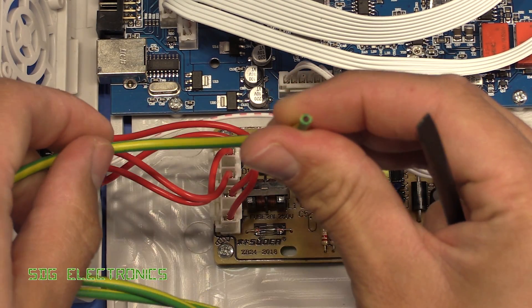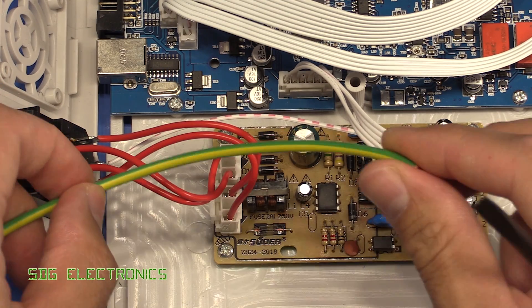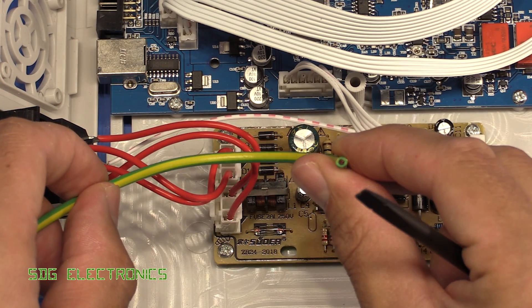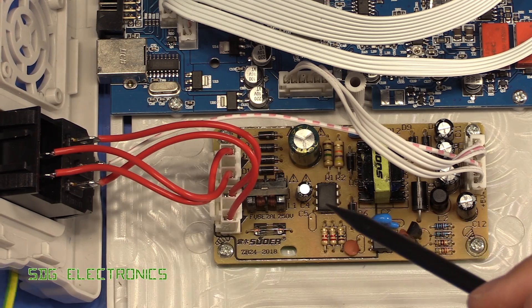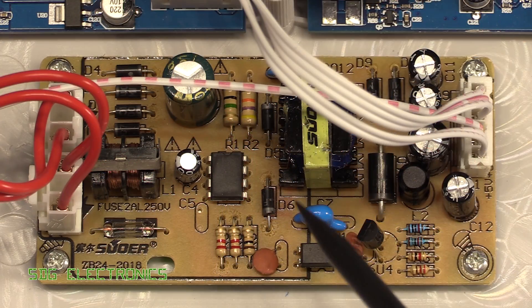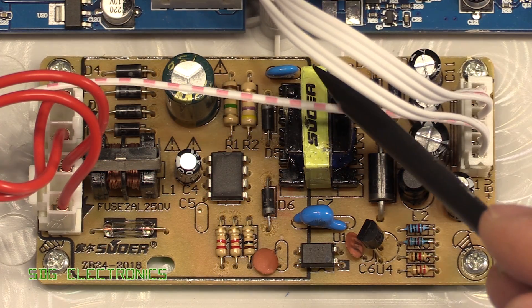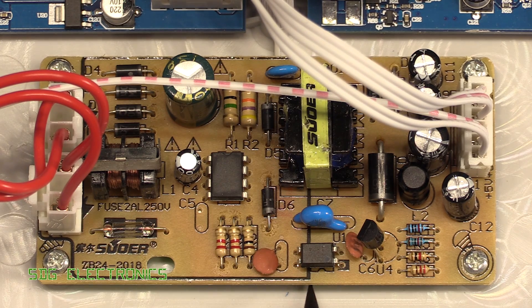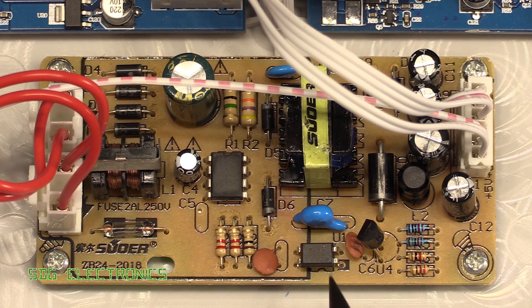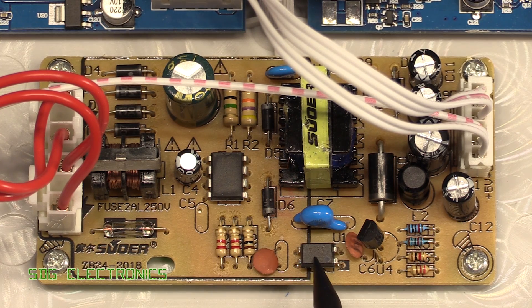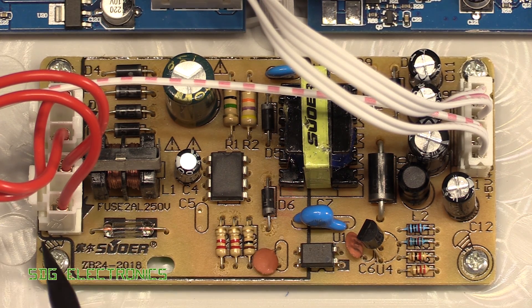I think we'll have to fix that. I've got some mains wire that has the correct insulation thickness and is designed for that purpose, so we'll swap this out. The actual power supply looks fine with the isolation here and you can see they've drawn a box around that side of things. There's only the transformer, the safety cap, and the opto-isolator bridge in that gap.